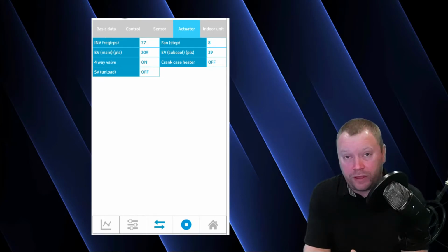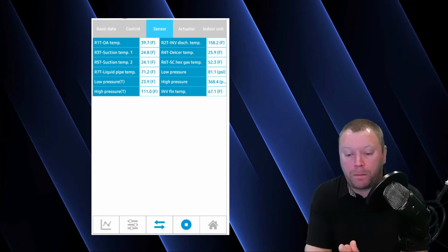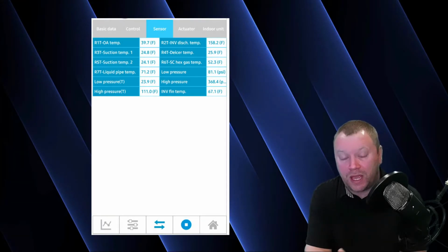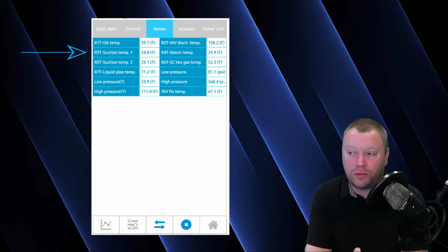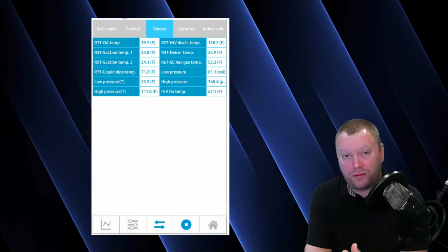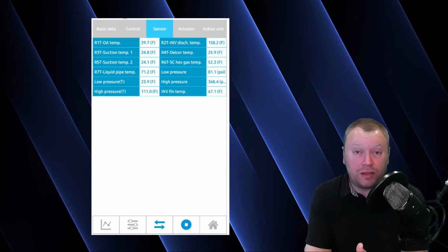Okay, so with the 4-way valve energized, the next location that our refrigerant should be traveling to from the 4-way valve is directly to the indoor unit. Now, what I like to do is verify my 4-way valve is doing its job. Make sure that there is no bleeding through the 4-way valve into the suction line or through my outdoor unit heat exchanger. And you can do this if you go back to the sensor tab by quickly looking at your heat exchanger temperature. In this case, it's called the de-icer temperature. That is the liquid temperature traveling into the heat exchanger from the liquid pipe. And then you can also look at your suction temperature. You can see that our suction temperature and our de-icer temperature are both very cold. Therefore, we can infer that there is no hot gas that is leaking through the 4-way valve to either of these components. So we can go to our indoor unit next because that is where the refrigerant will be traveling to next.